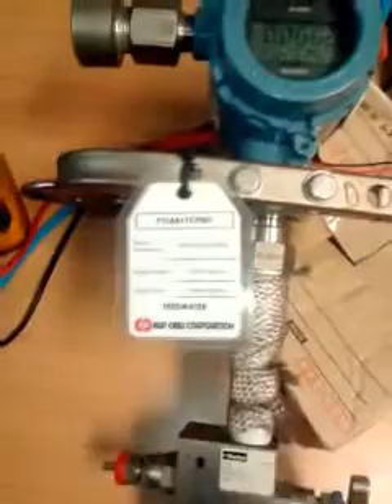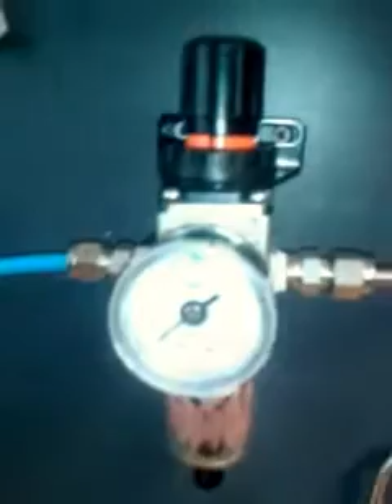So we will try to zero trim or sensor trim this one to make it 0, since there is no pressure applied in the transmitter. No pressure. Look, okay. Look at the regulator, 0. Look at the test gauge, also 0. Meaning there is no pressure applied to the transmitter. So the display should be 0 also. But here there is just a small value. To make it 0, we will try to sensor trim using the HART communicator. Okay, sensor trim.